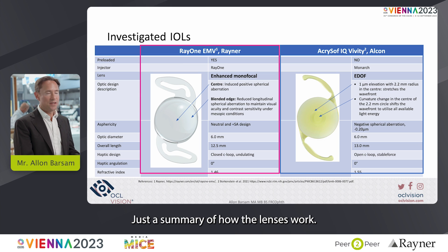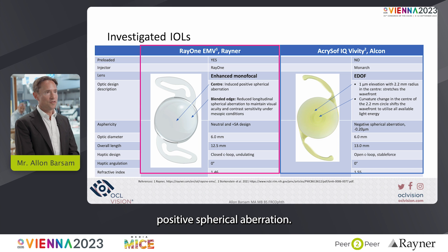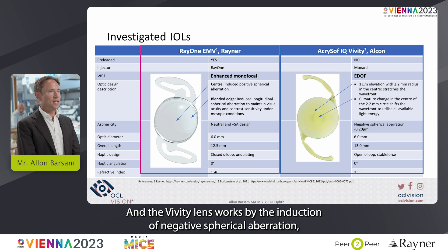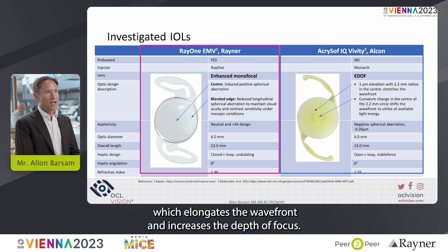A summary of how the lenses work: the RayOne EMV lens works by the induction of small amounts of positive spherical aberration, and the Vivity lens works by the induction of negative spherical aberration, as well as an elevated portion of the lens which elongates the wavefront and increases the depth of focus.